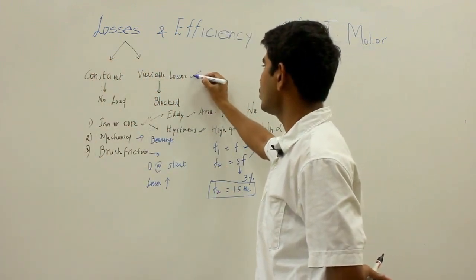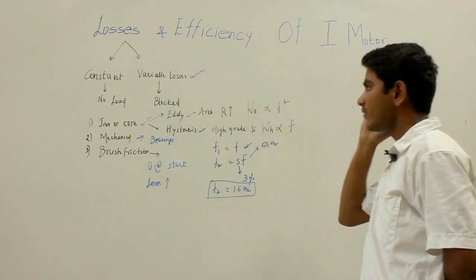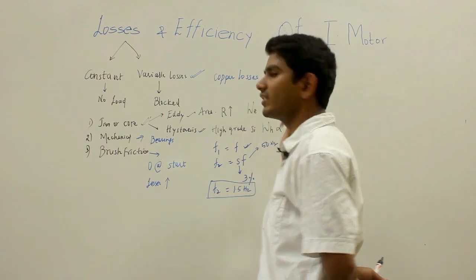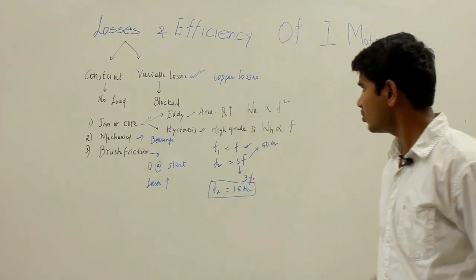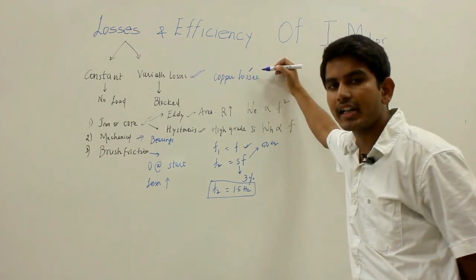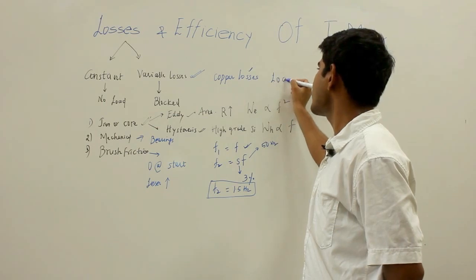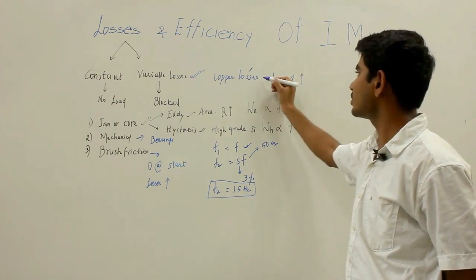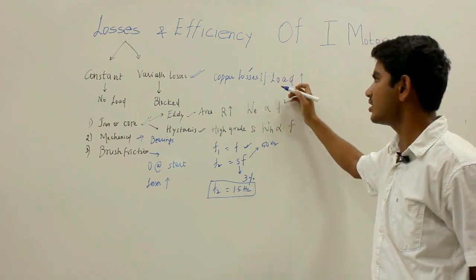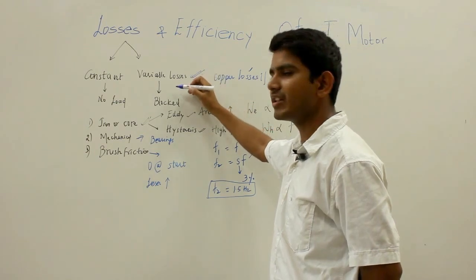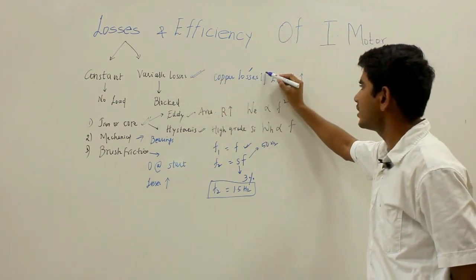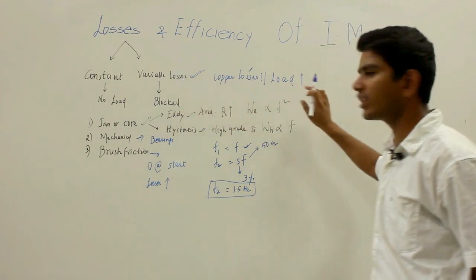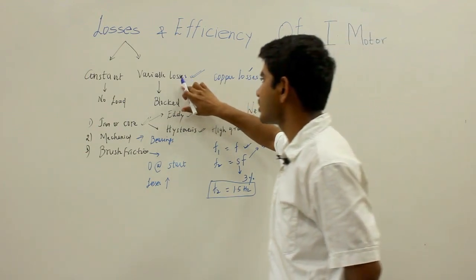Variable losses can also be called copper losses. These losses occur due to the current flowing in the stator winding as well as the rotor winding. As you vary the load connected to the shaft, the current flowing through the stator and rotor windings changes — and since this current keeps varying with the load, these copper losses are referred to as variable losses.